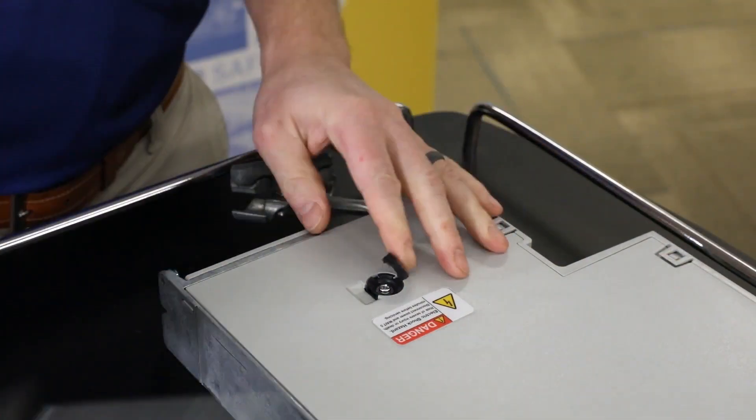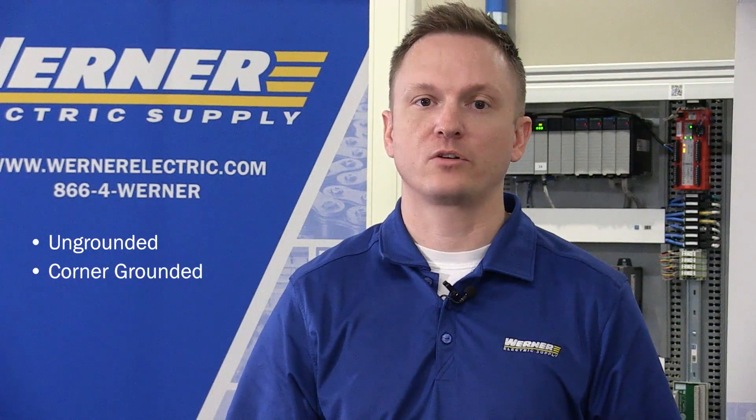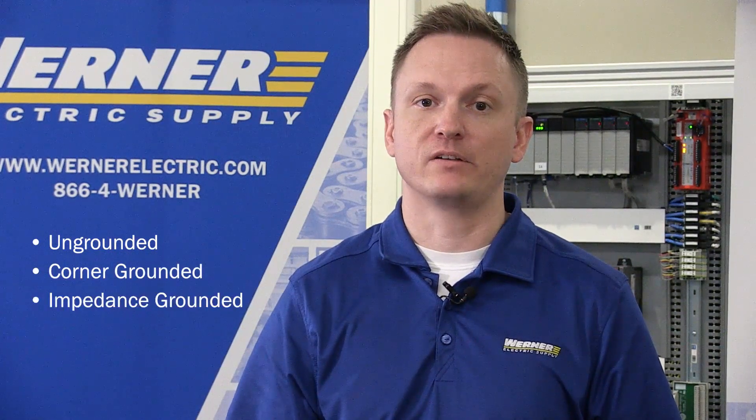The only times you would not install the grounding screw is if your incoming three-phase power configuration was of the following type: ungrounded, corner grounded, impedance grounded, or a regenerative power supply converter.